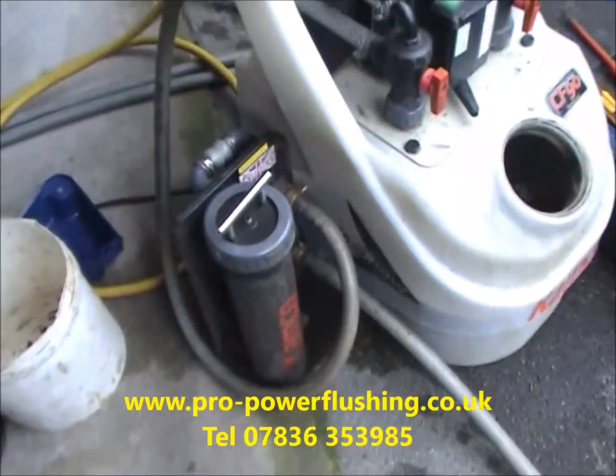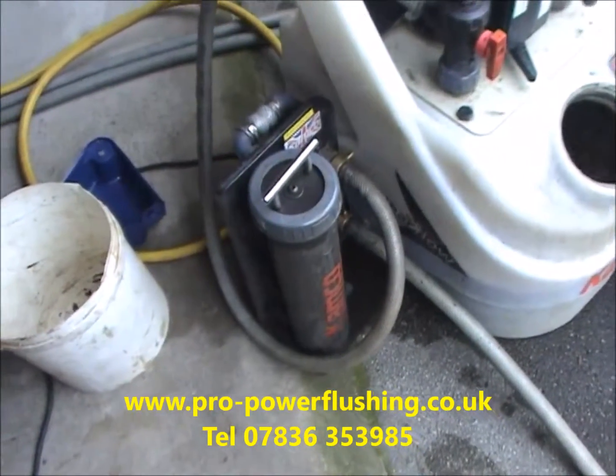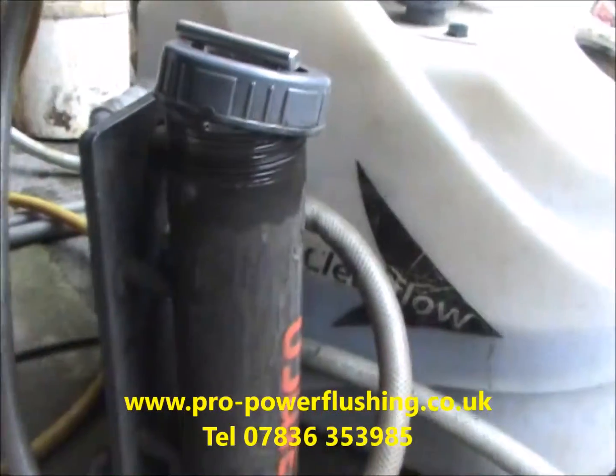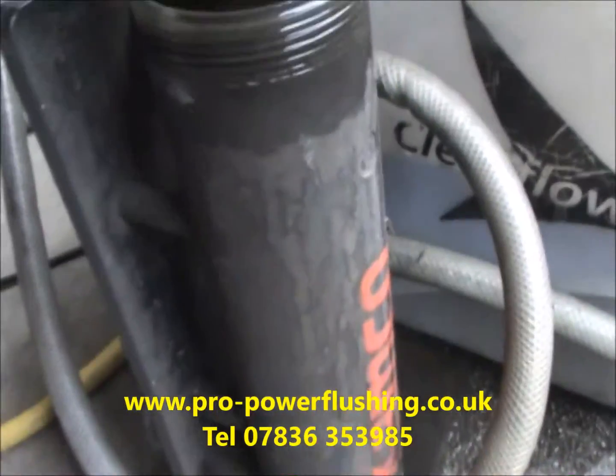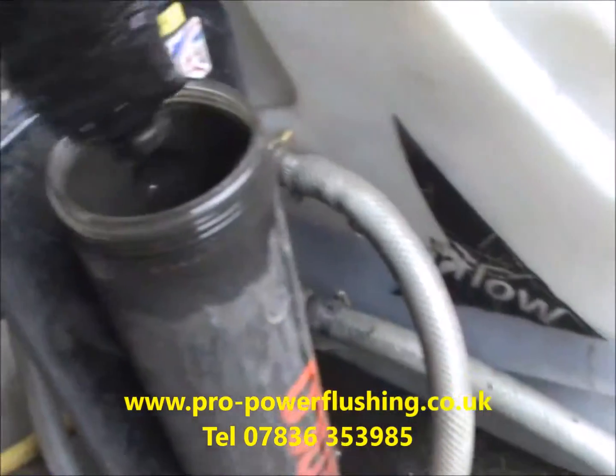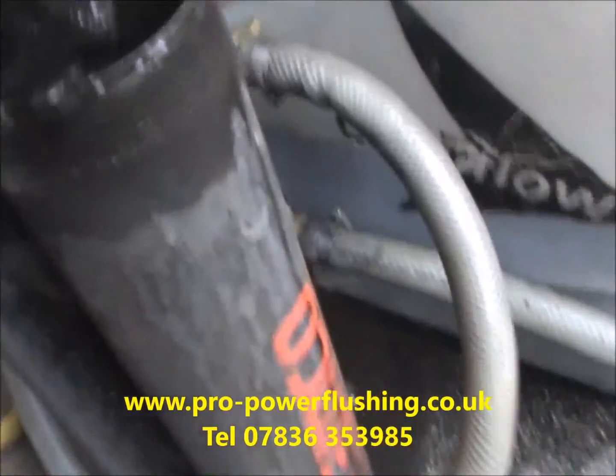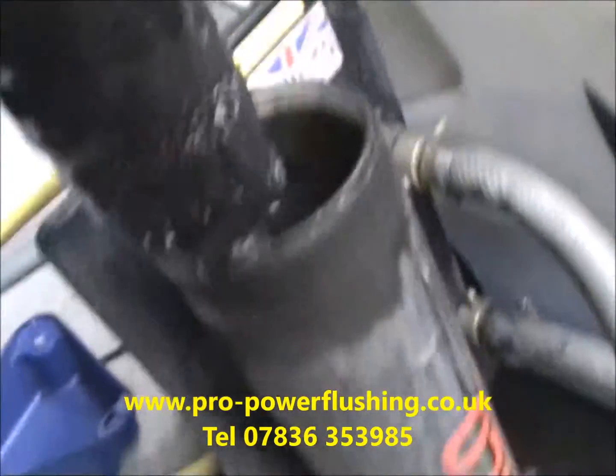Okay, so we'll show you that. We're just going to put this on bypass and we'll take it out and we'll show you that magnet. Okay, we've undone it, we've put it on bypass, we've not looked at it yet, so let's take a look. Oh yeah, wow. I can hardly pick it up, it's so heavy and so full of corrosion. Now that is absolutely unbelievable. We'll just rest it against there.